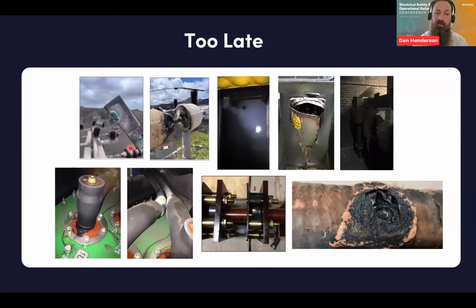Same with an insulator there, which was corroding and then broke down and failed. And then these are all similar, where we've had compound fill boxes. There's been a void in there, and then it's got to a point where that PD has tracked across, and you've had an earth to earth, a phase to earth fault. We've had a circuit breaker failure, a transformer failure at a separate time, and this is a junction box failure.